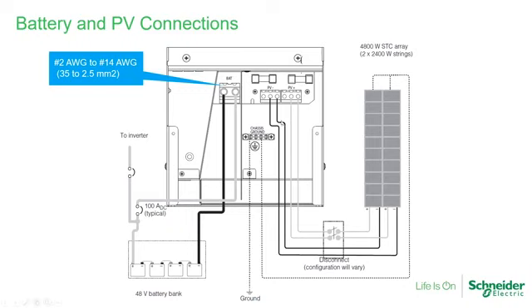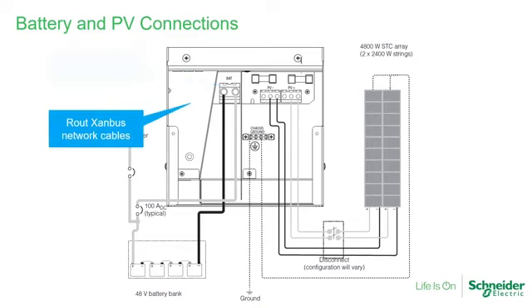On the other side, on the battery side, you'll immediately notice that the connector is much bigger and can handle a much bigger conductor, of course, because now we've moved down from 600 volts, which is on the PV side. When the voltage is higher, the conductor is smaller because you're carrying less current. Now on the battery side, the voltage is a nominal 48, so you'll have more current. And this will accommodate from a number 2 to a number 14.